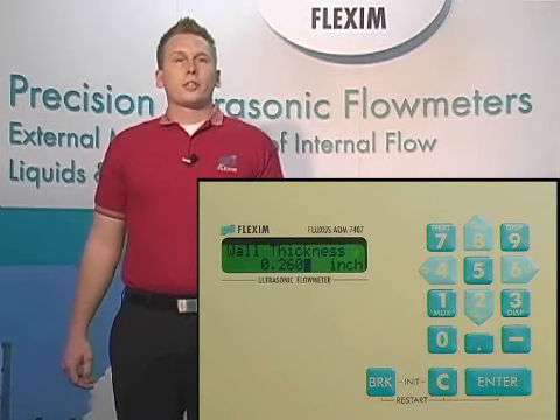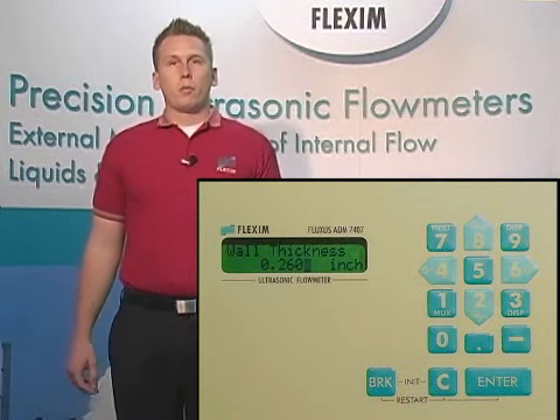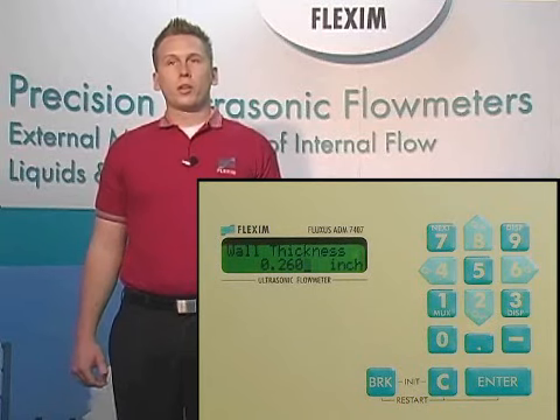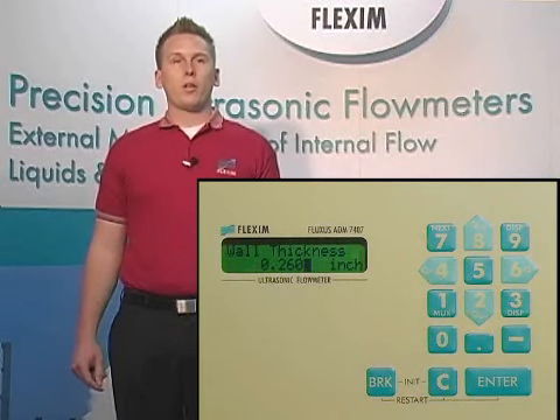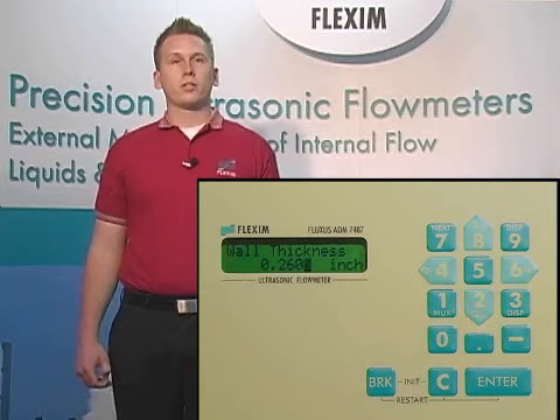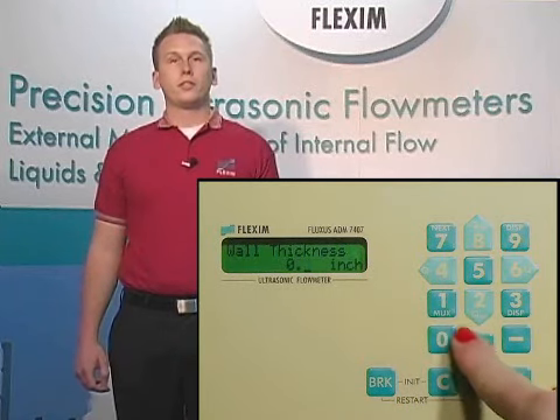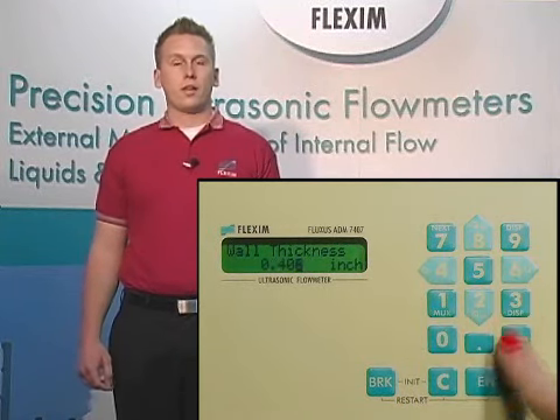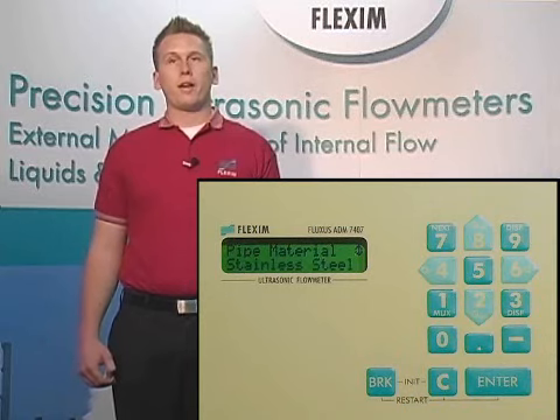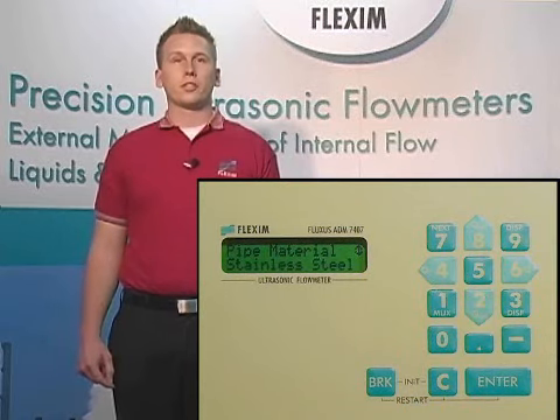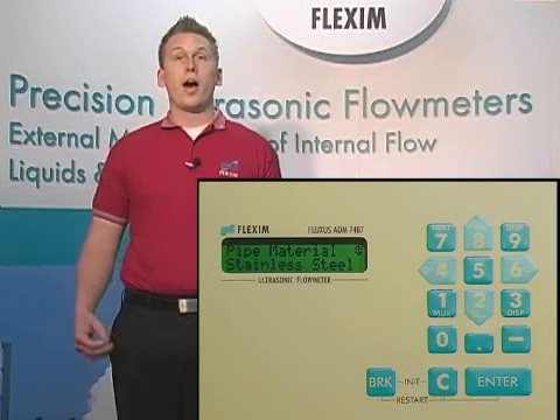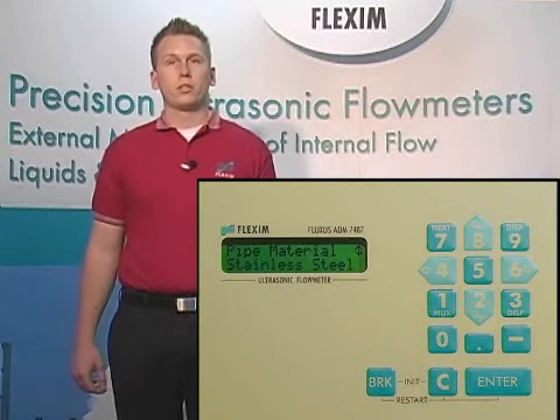Now we need to enter the actual wall thickness of our pipe. From a pipe chart, we see that a Schedule 40 carbon steel pipe has an actual wall thickness of 0.406 inches. So we enter 0.406 and hit enter. The other option we have here is to use our wall thickness gauge to get a more accurate measurement. We highly recommend this option if it's available.